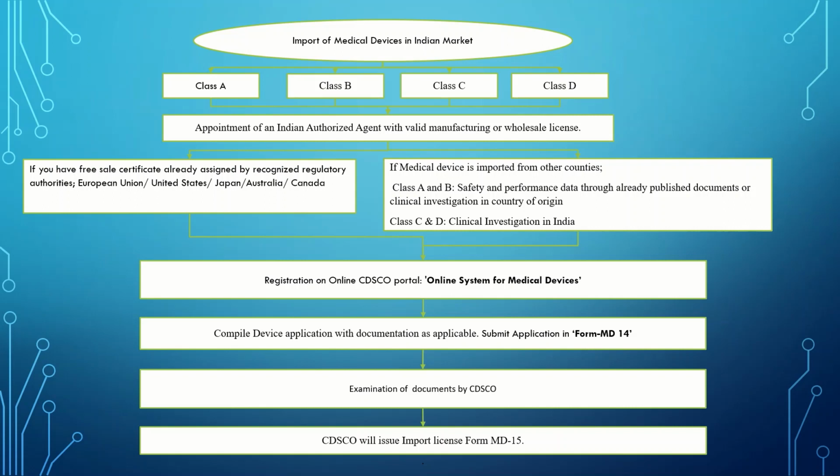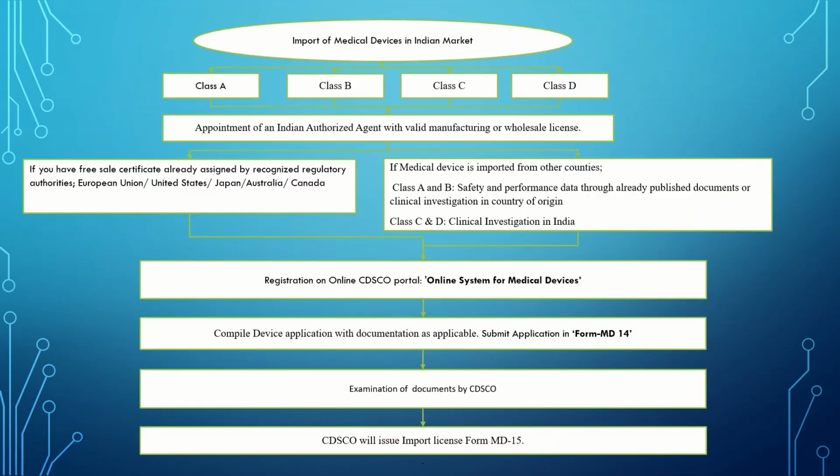Now the next step is to appoint an authorized agent in India. The authorized agent means a person including any firm or organization who has been appointed by an overseas manufacturer through a power of attorney to undertake import of medical devices in India. One of the mandatory requirements is that the authorized agent shall have a valid manufacturing license or wholesale license issued by CDSCO.